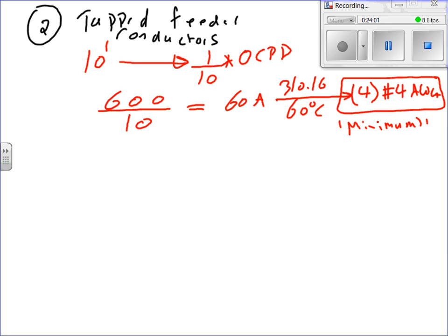Can you guys write this is the minimum conductor size? Can I tap higher than that? 1/0, 2/0, bring it on. No problem. It's not smart, but I can tap 2000 kcmil out of 500 kcmil if I want to, as long as I protect them. It doesn't make sense.